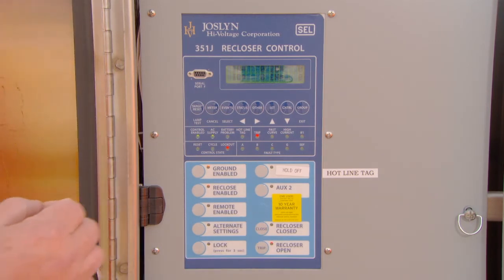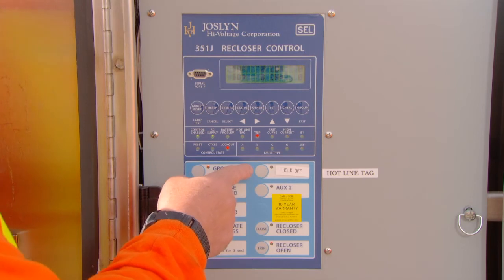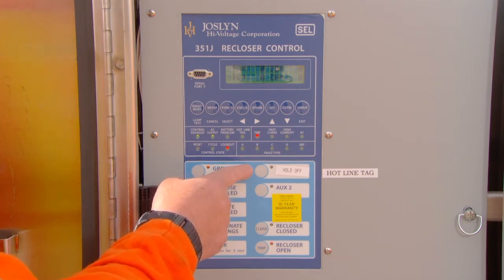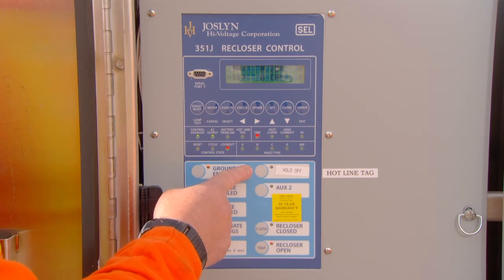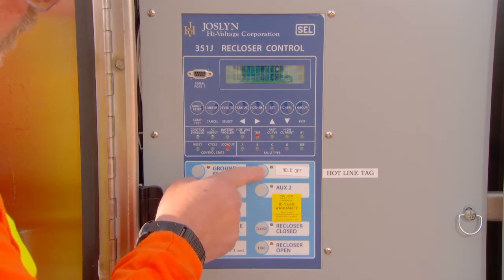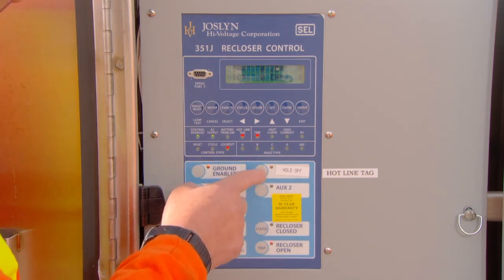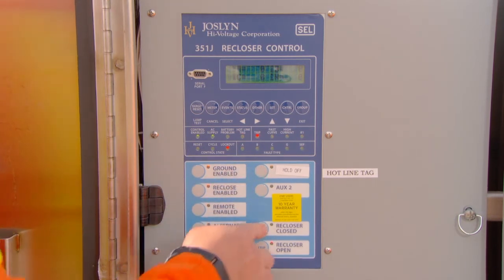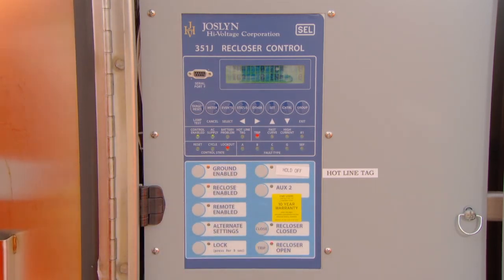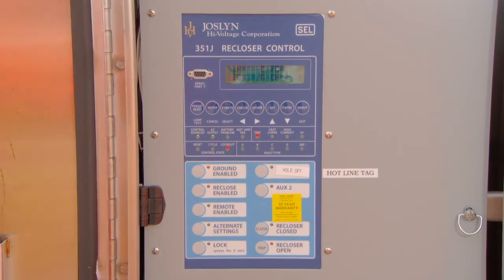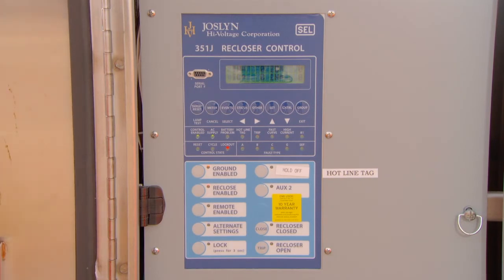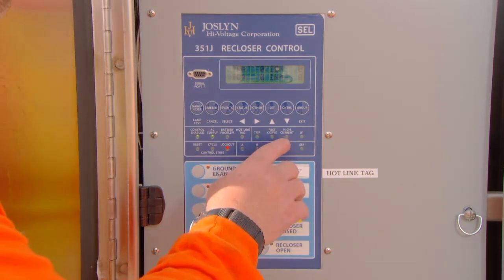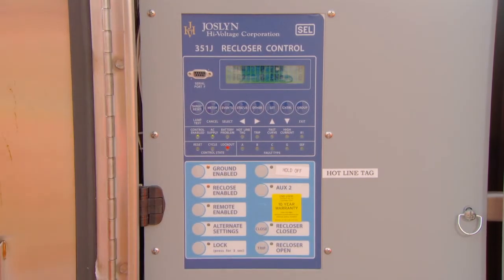A note about the high current and the normal trip current setting. If you were setting the normal trip current value in this unit, you would set it for a threshold that would coordinate with downstream devices. On the other hand, high current is typically set when a unit is placed very close to a station where the fault currents available at that location are above your desired threshold setting. If the high current value is exceeded, you get an instantaneous one-shot to lockout trip, regardless of the settings. You do not want the unit to follow a cycle of multiple reclose attempts.